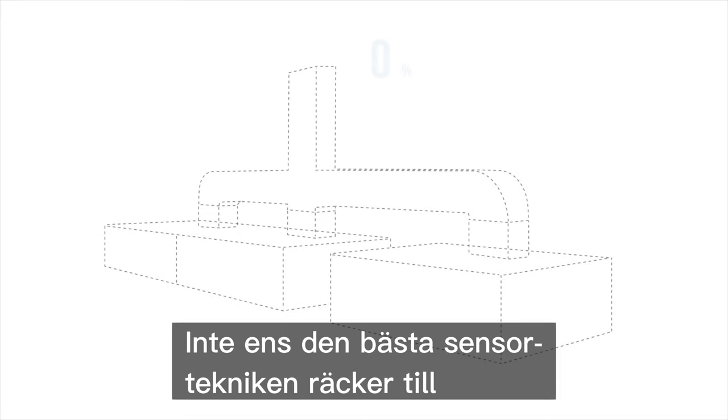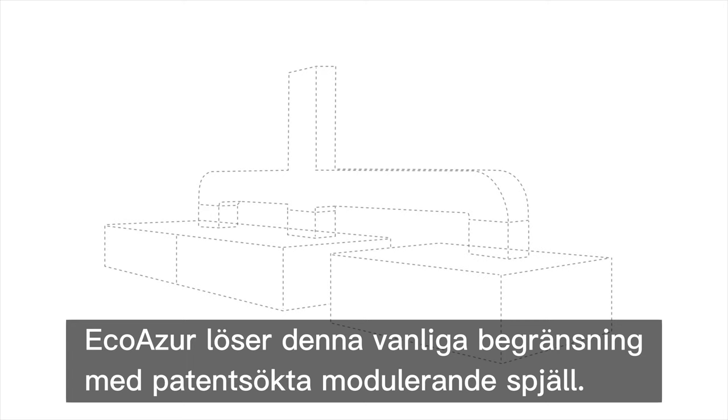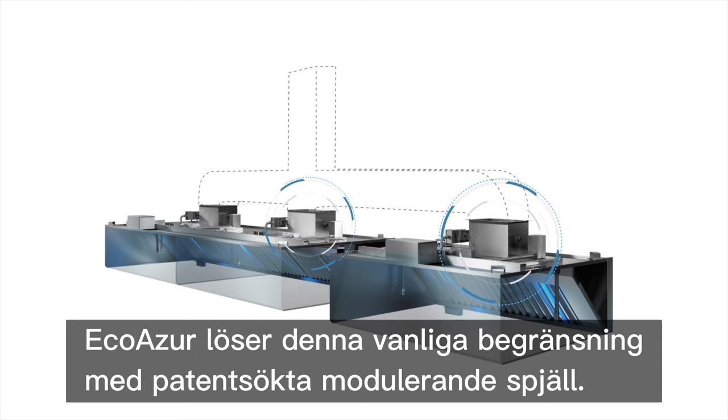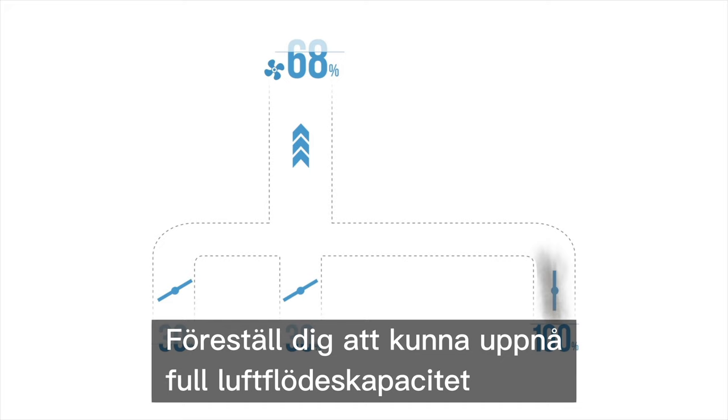Even the best hood sensor technology may not be enough when multiple hoods share a common exhaust fan — the overall exhaust airflow will always be driven by the most demanding hood. EcoAzur overcomes this common design constraint with its patent-pending modulating dampers. This technology independently controls the exhaust rate of each hood and generates outstanding energy savings. Imagine being able to achieve full airflow capacity of a hood in less than four seconds while saving on all other hoods.